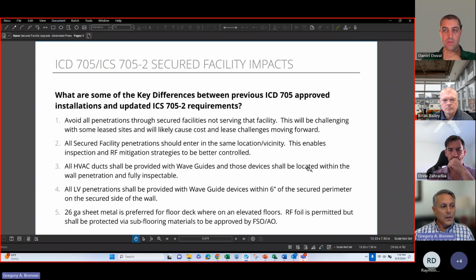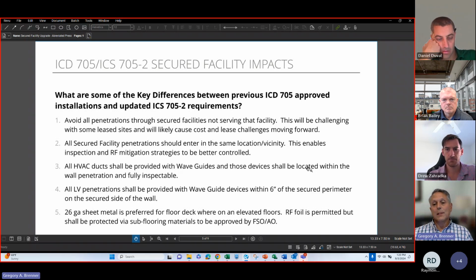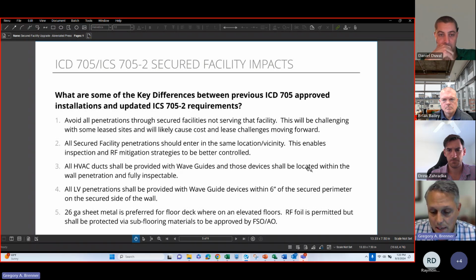Avoid all penetrations through secured facilities that are not serving that facility. That's not necessarily a new requirement, but it is being enforced more rigorously—where you can move ductwork or landlord base building trunk ducts out of that space, do it. Make sure you're planning on it, make sure you're capturing it in the cost, because encapsulating it, while it is an approved strategy, if you can move it, they're pushing us to move it.